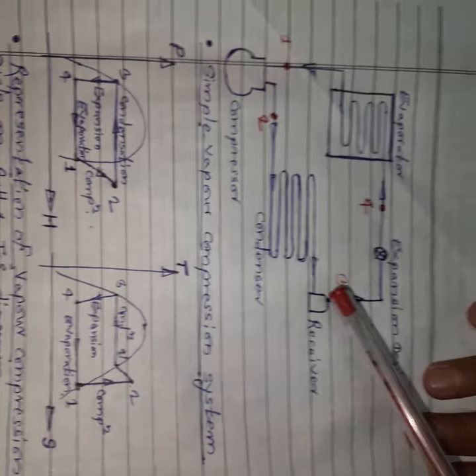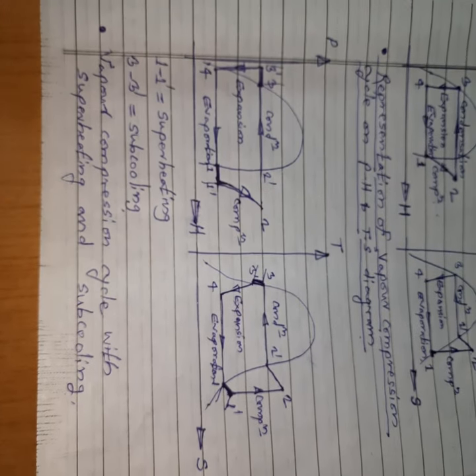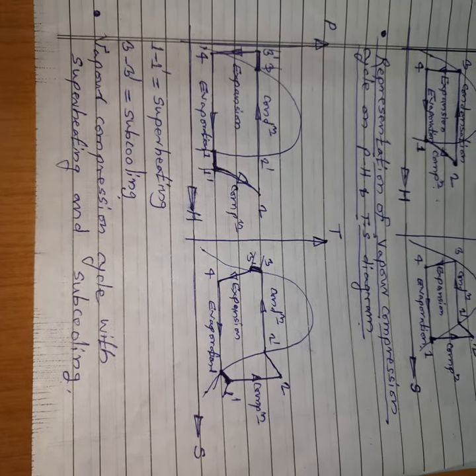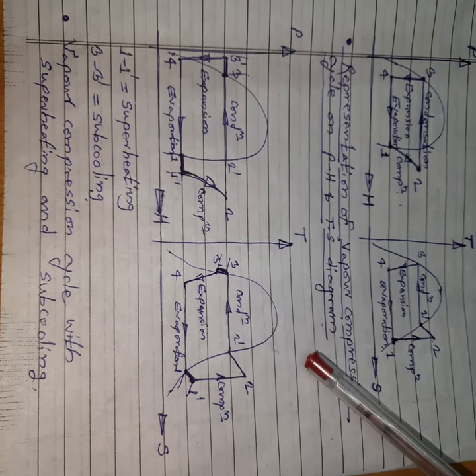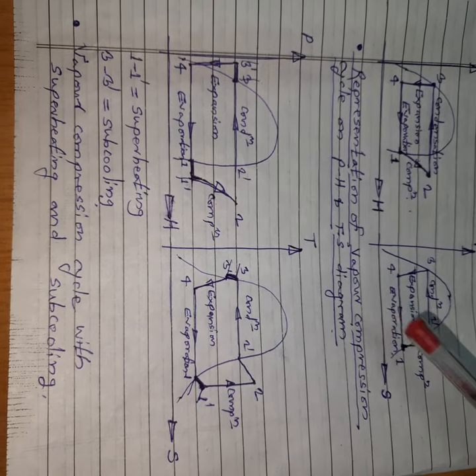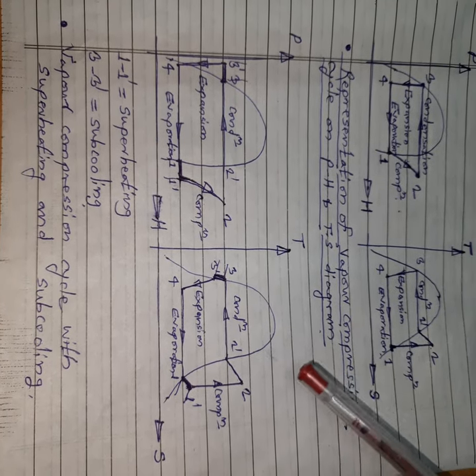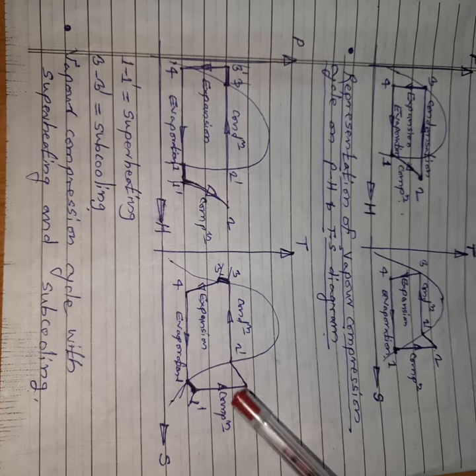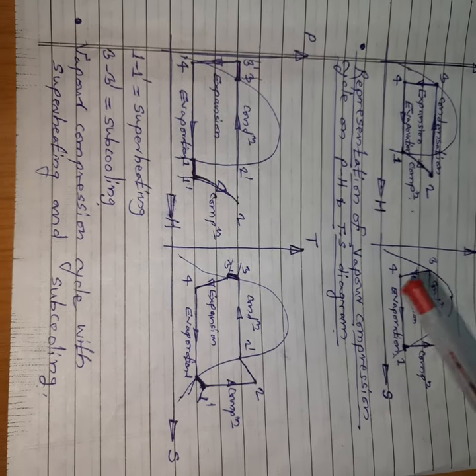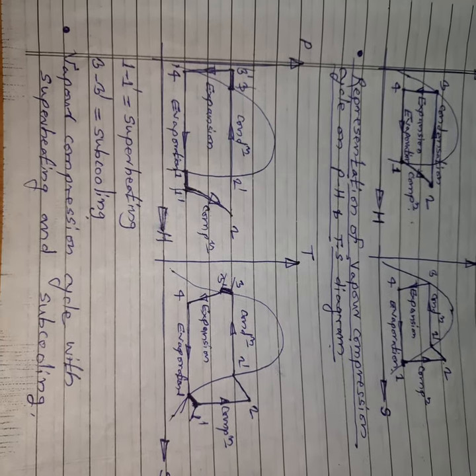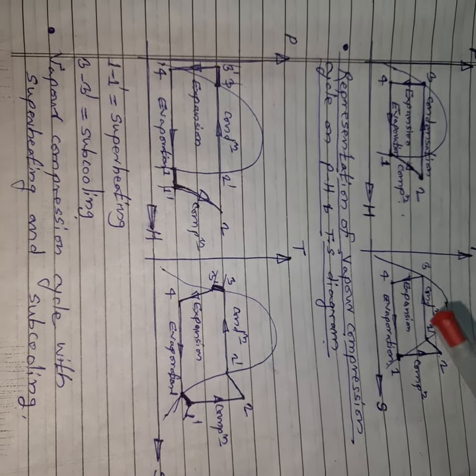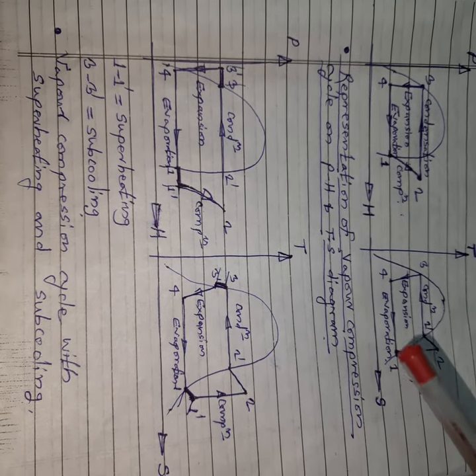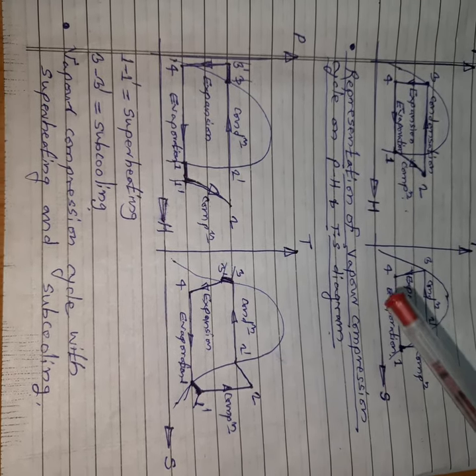In the vapor compression cycle, there are two important terms: superheating and subcooling. Because of superheating and subcooling, the coefficient of performance of the vapor compression cycle increases. Superheating means increasing the temperature of the refrigerant above saturation temperature. Subcooling means decreasing the temperature of the refrigerant below saturation temperature.